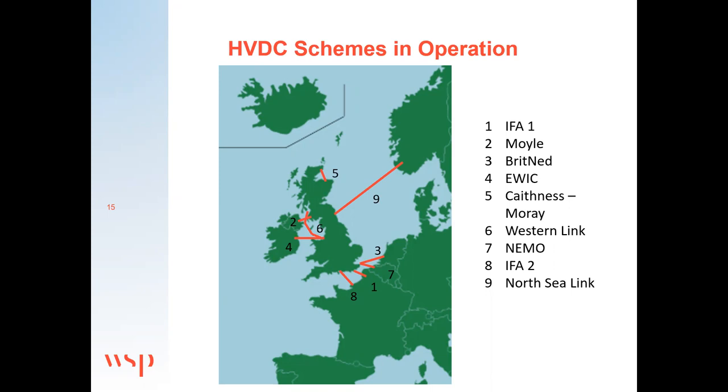The first scheme built was the IFA1 scheme. It's been in service for, where are we now, 35, 36 years. It's recently had a major refurbishment of its power electronics, controls, cooling systems, transformers, to extend its life. So these stations would have a natural lifetime of 40 years, but you can extend the life by another 20, 30 years just by replacing some of the equipment.